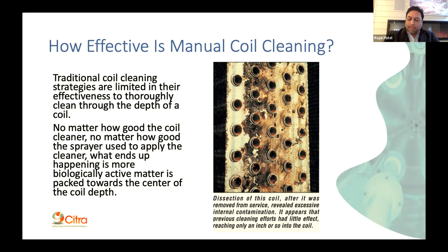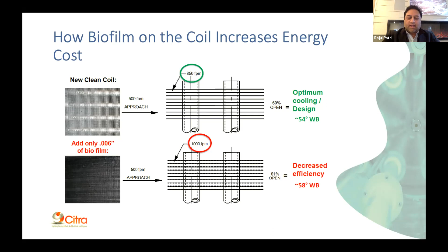And how that biofilm actually increases costs, right? If you have a brand new coil system, top left, designed at 500 feet per minute airflow, when it goes through the fins, that air velocity accelerates to 850, and you're achieving 54-degree wet bulb temperature there. Now, on the bottom, we're only adding 0.006 of an inch of biofilm, and the results are air velocity has increased to 1,000, and we've lost efficiency. A 4-degree difference with just 0.006 of an inch of biofilm.